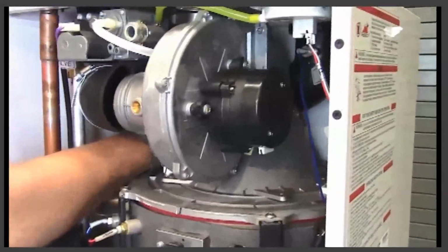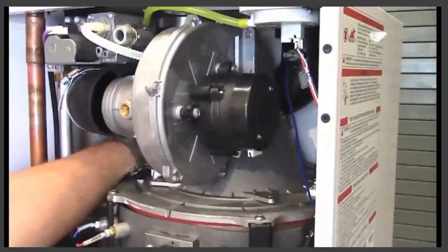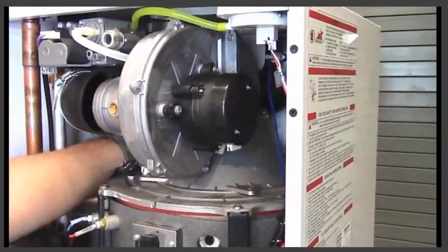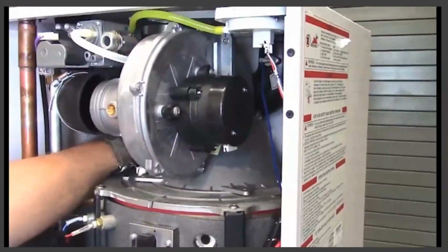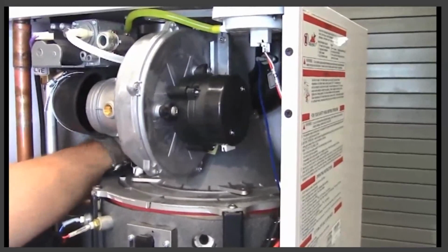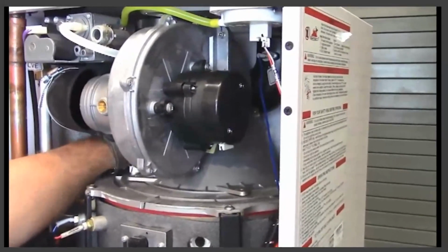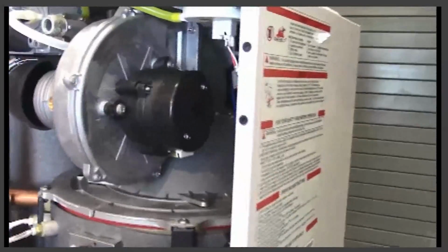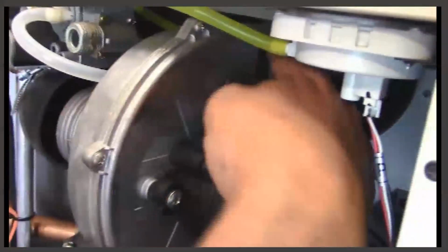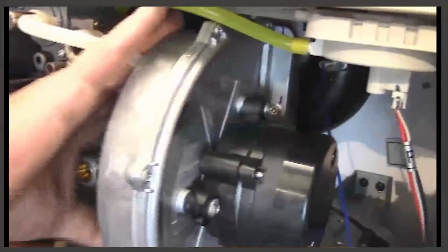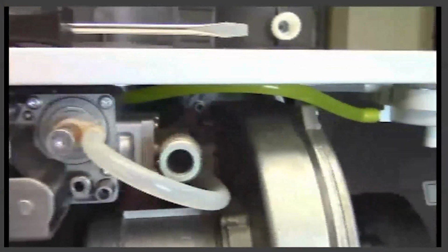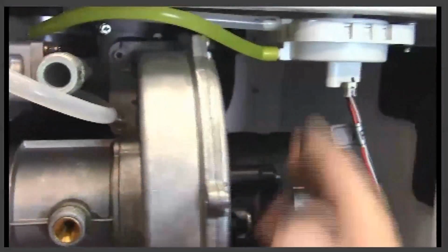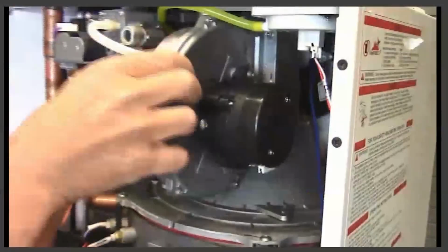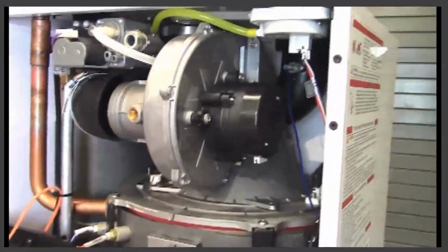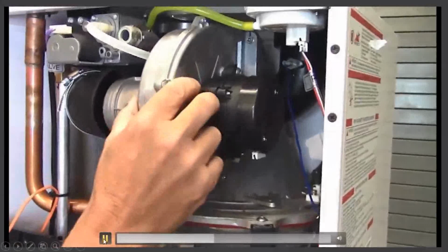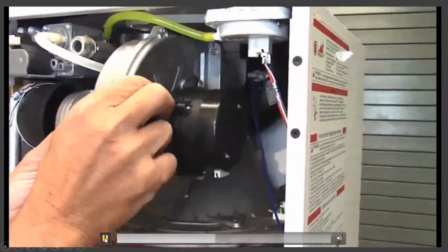So Ken is removing, on the 199, the blower and plate all as one. On the smaller size boilers, such as the 140, with the headroom, you will not be able to get the blower and plate all out as one. So you will have to remove the blower from the arm, which entails removal of the 4 10mm nuts, 2 up top and 2 on the bottom. Then take the blower out and separately remove the arm. But in this example, this is a 199 combination. You'll pull all of it out in one piece.